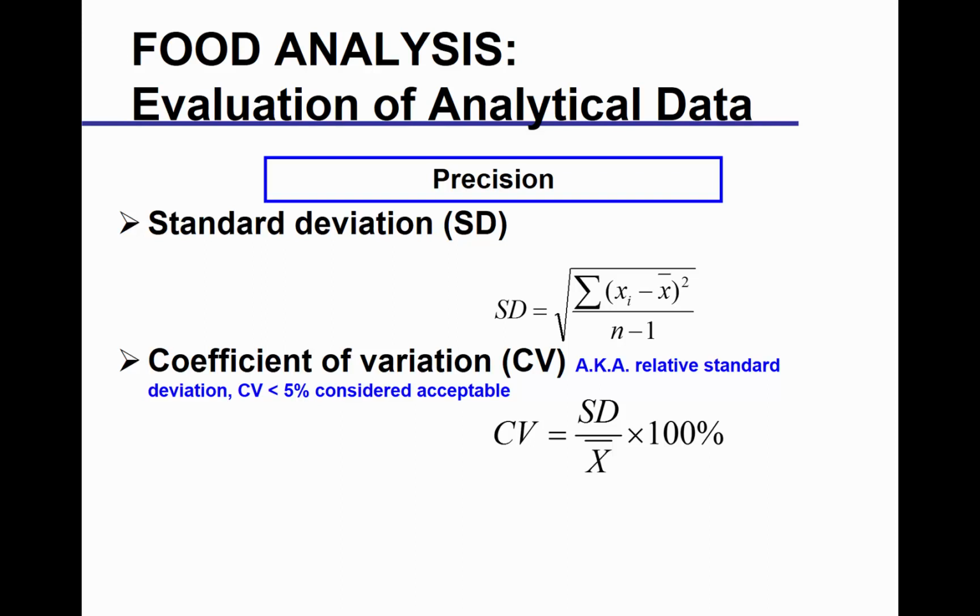So would you always factor in the coefficient of variation? Sorry? Would I always factor that in? The coefficient of variation? Yeah. No, you can, but what I was saying is, if you are just comparing the same sample with two different methods, you don't have to do CV. You do not have to calculate it because it's the same sample, basically a similar average.